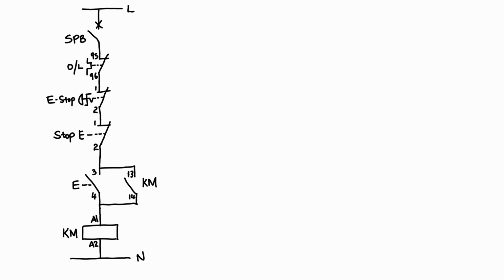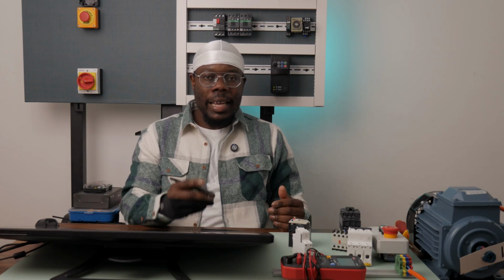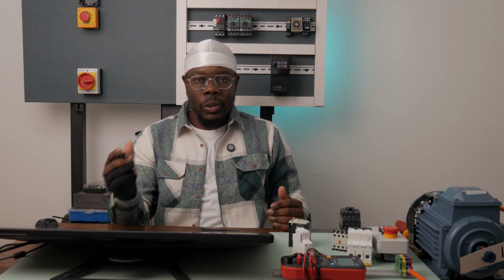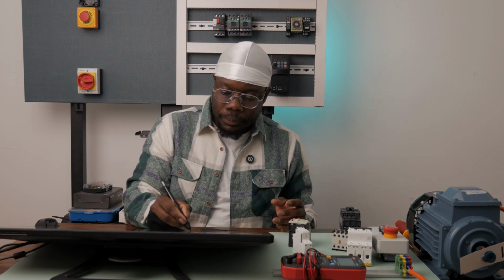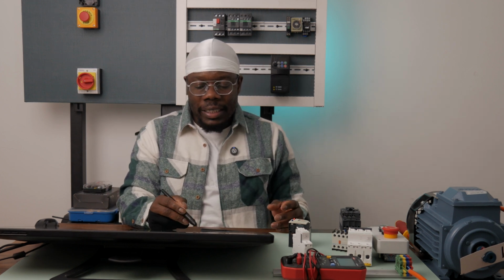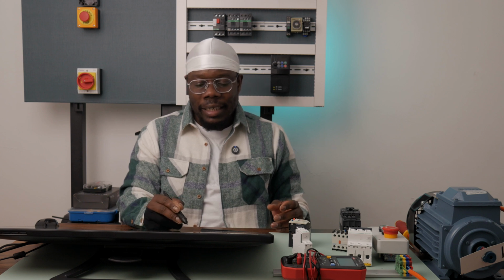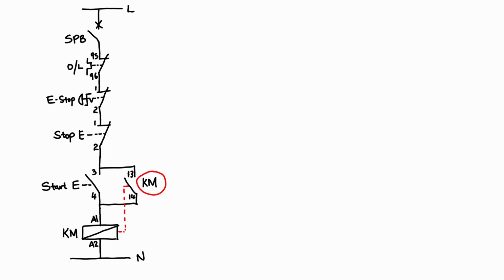One other thing that we should always remember is contactors are generally labeled KM. Some just label them K, but for a lot of people, K is reserved for a general relay. If you see KM, K stands for contactor, M stands for motor. So if it's KM, it tells you that it's a contactor that is being used to switch the power to an electric motor. The reason why I put KM on 13 and 14 is I'm indicating that this contactor coil, KM, is also the one that is going to operate this contact as well.